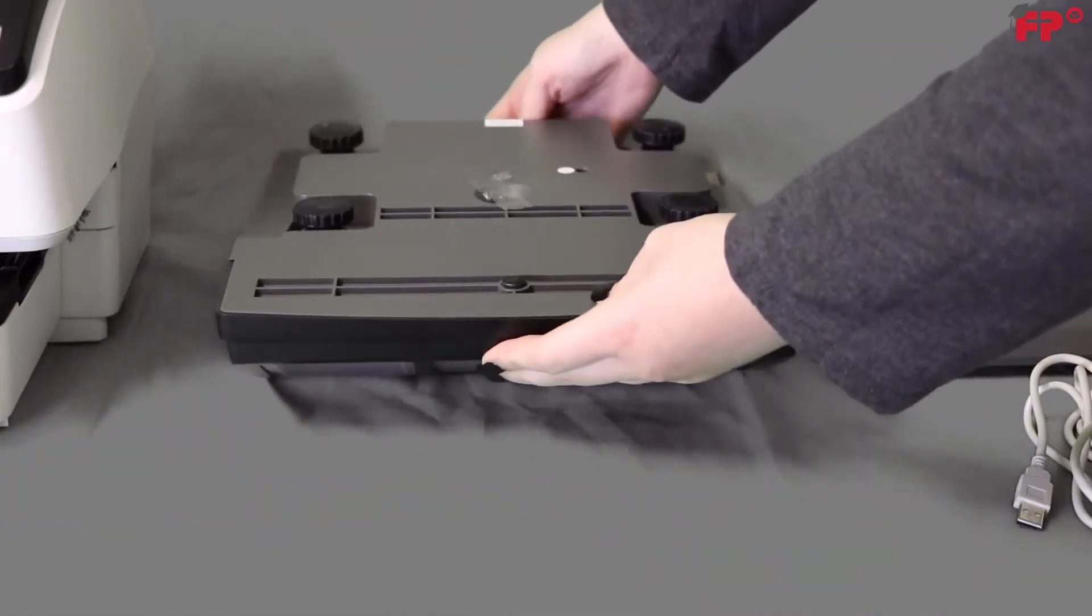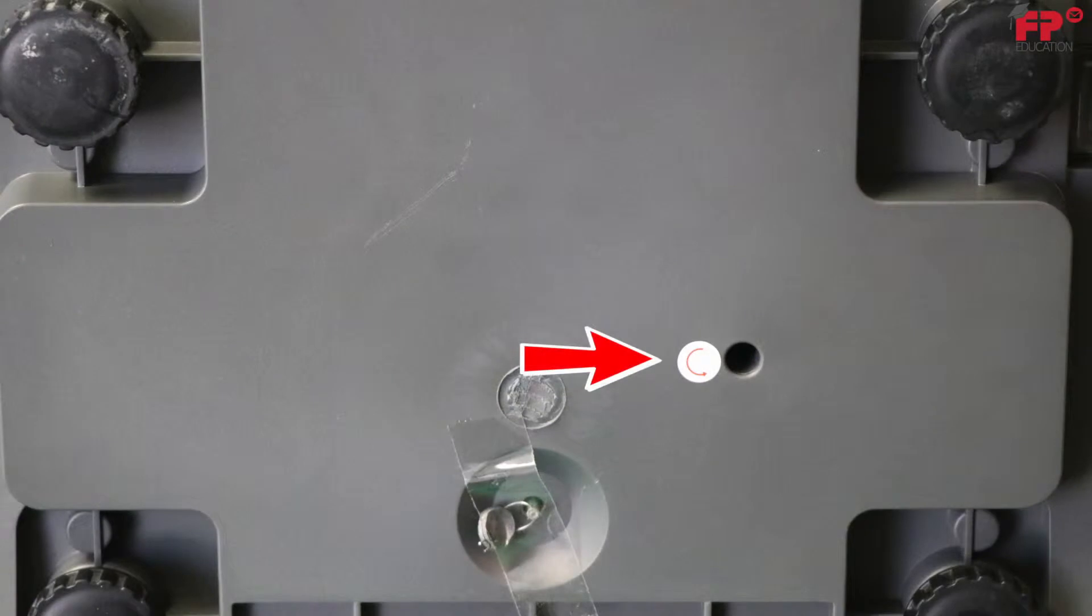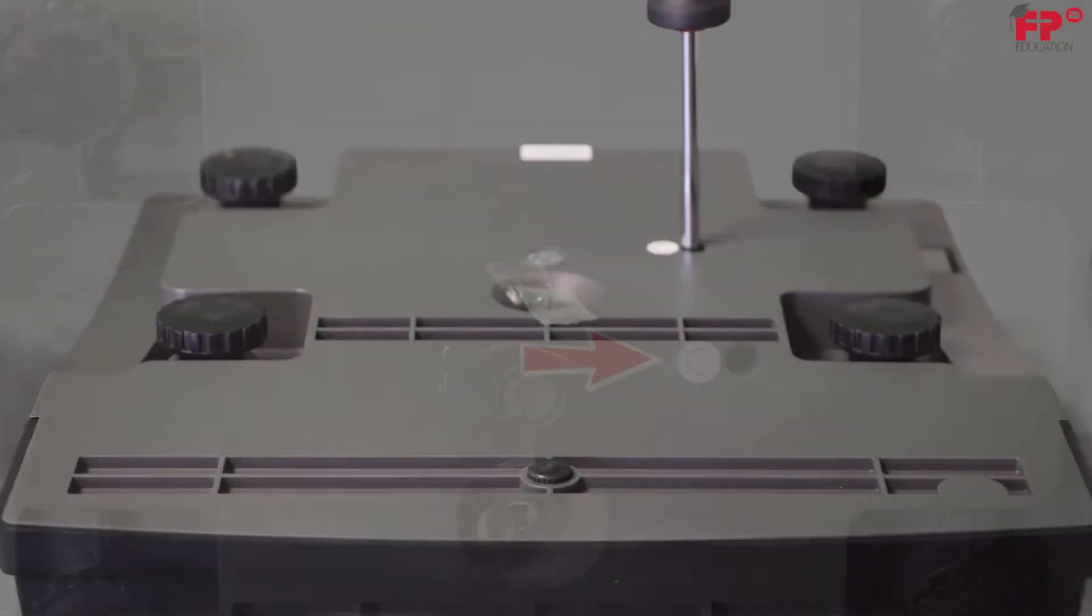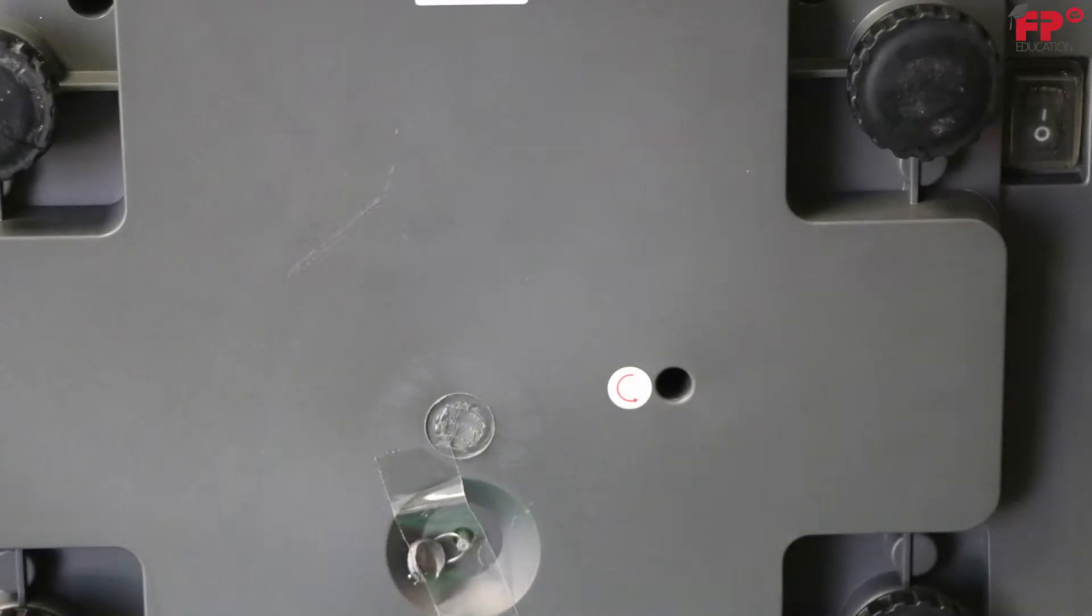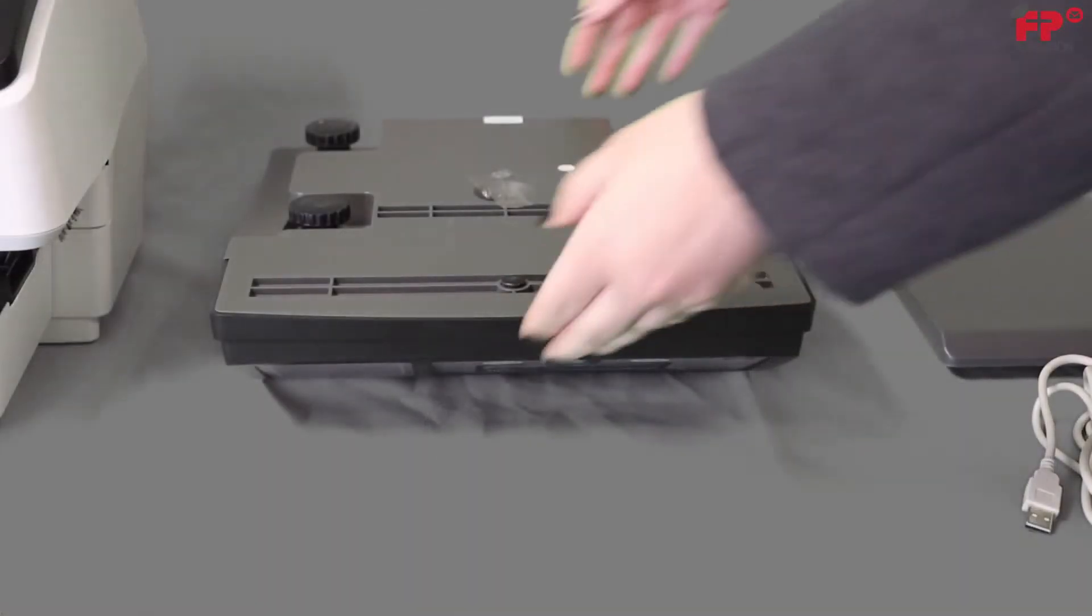Before plugging in the scale, turn the unit over. You will notice a sticker with a circular arrow. Grab a Phillips screwdriver and remove the load cell locking screw. Beware the power switch is located here. Do not turn it on just yet.